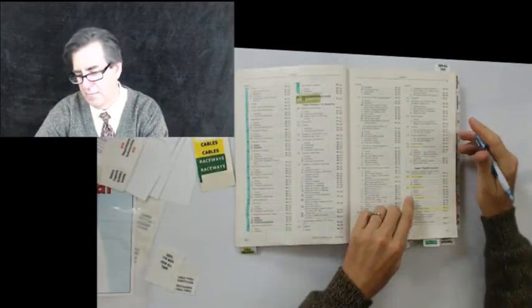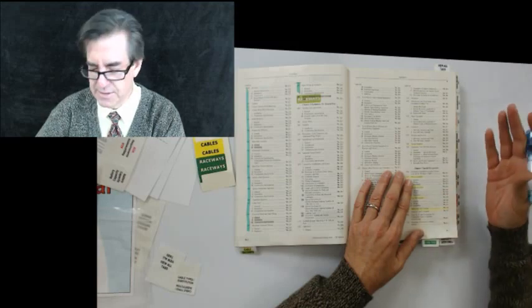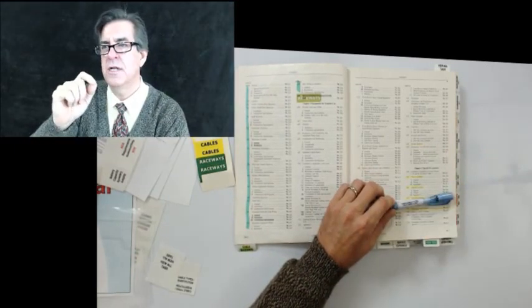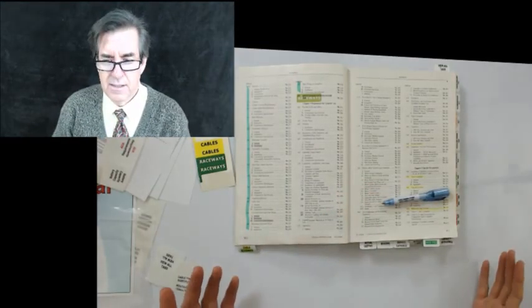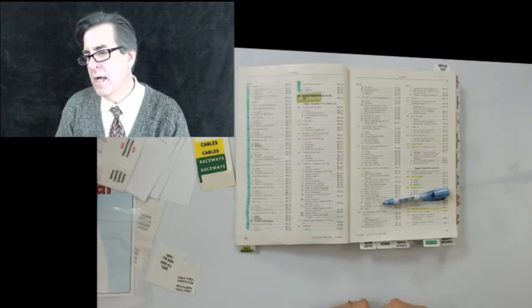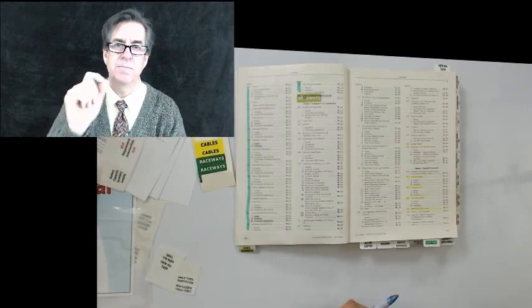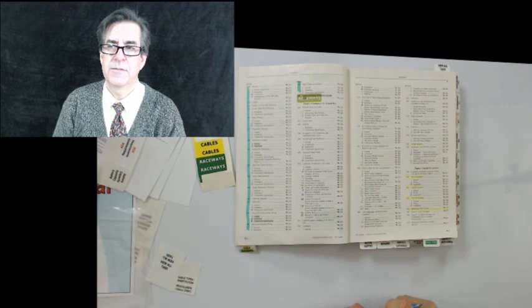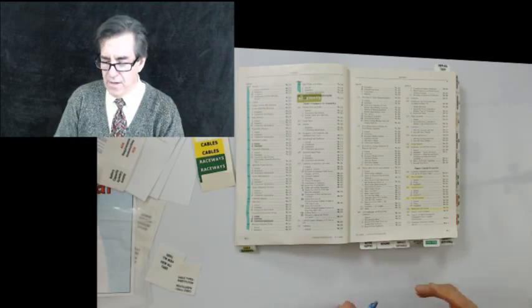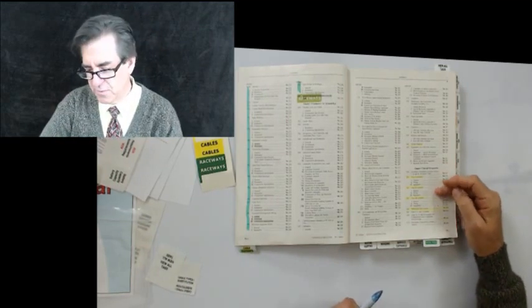Now chapter 5, special occupancies—I'm going to explain my tree and how I break this down in a little bit here. Special occupancies class 1, which is 501, is a type of occupancy that has a specific type of flammable dust, liquid, or fumes, or what they call flyings. These three locations differ only in the type of explosive material produced in the location. So if you have, say, a cotton mill, or a grain factory, or some place that has gasolines and produces paint fumes, those are the categories that relate to those specific types of hazardous substances that could be in the air or on the ground, and could be dangerous. We're going to go into those tomorrow, and I'll explain those to you. Once you see those, it's really simple to understand.